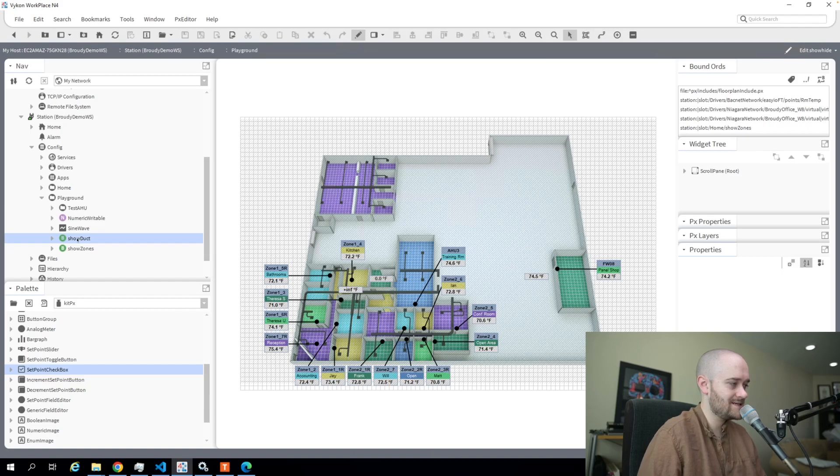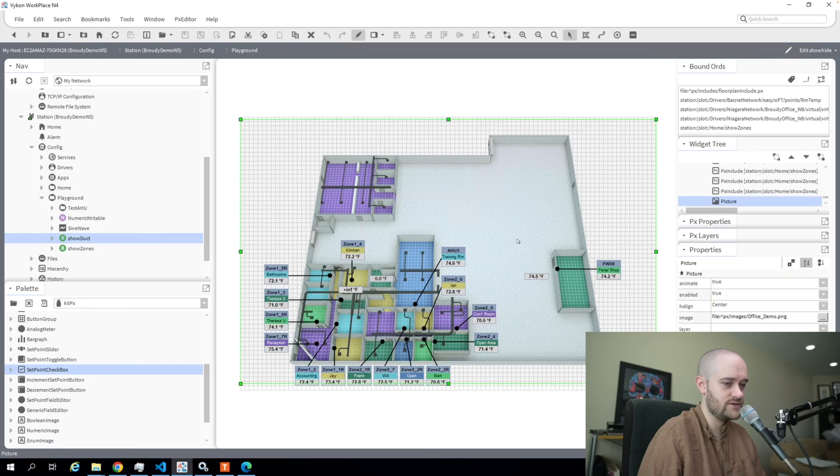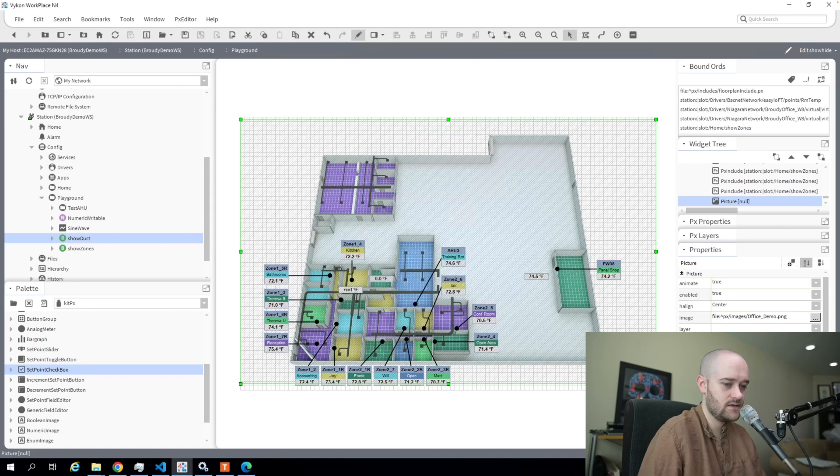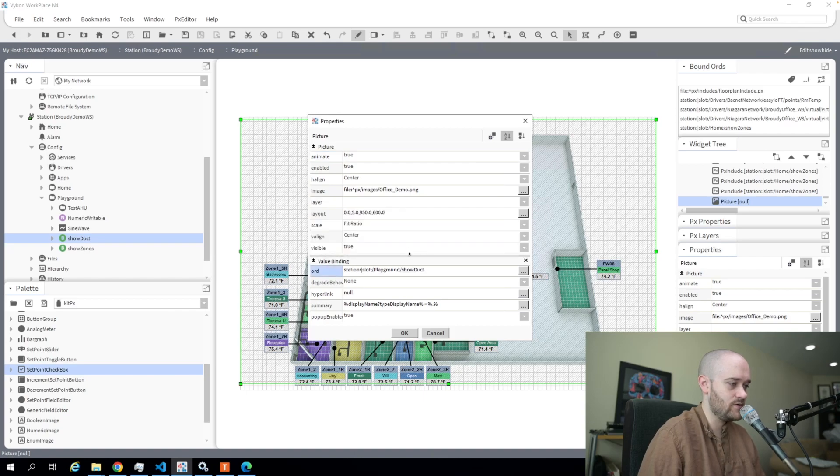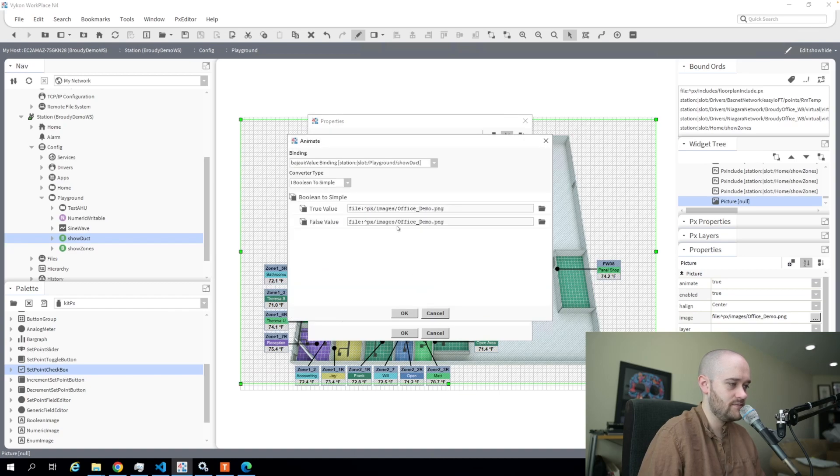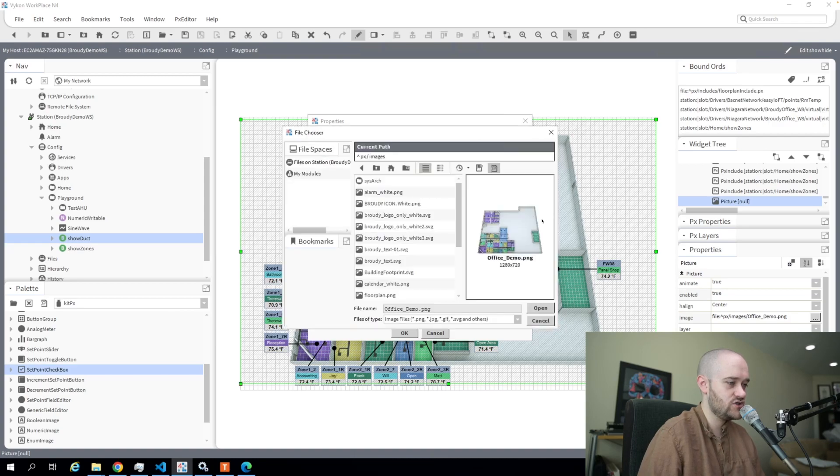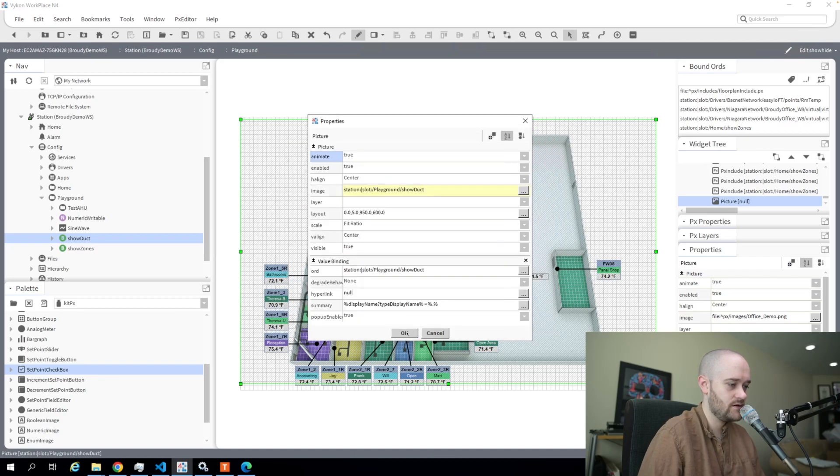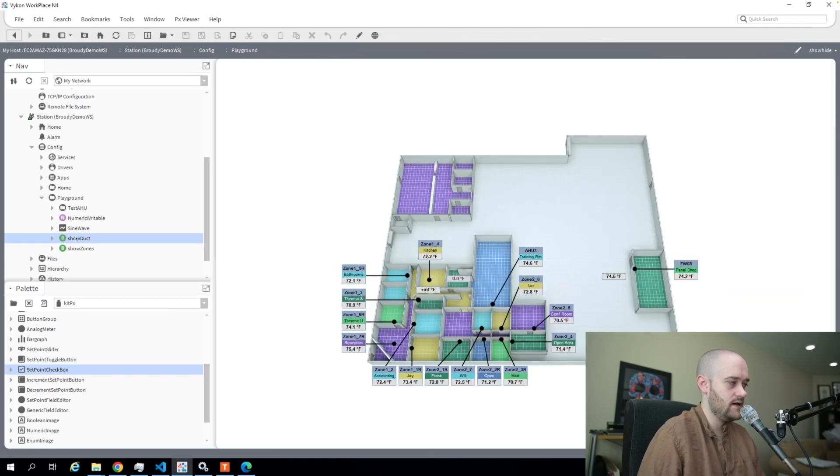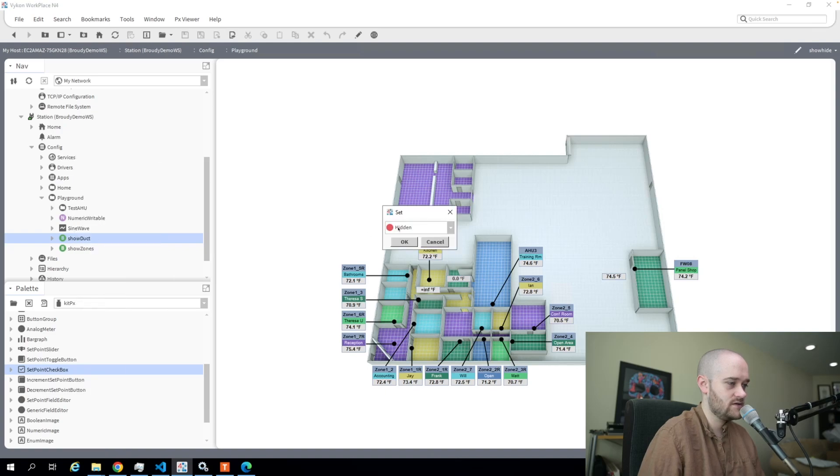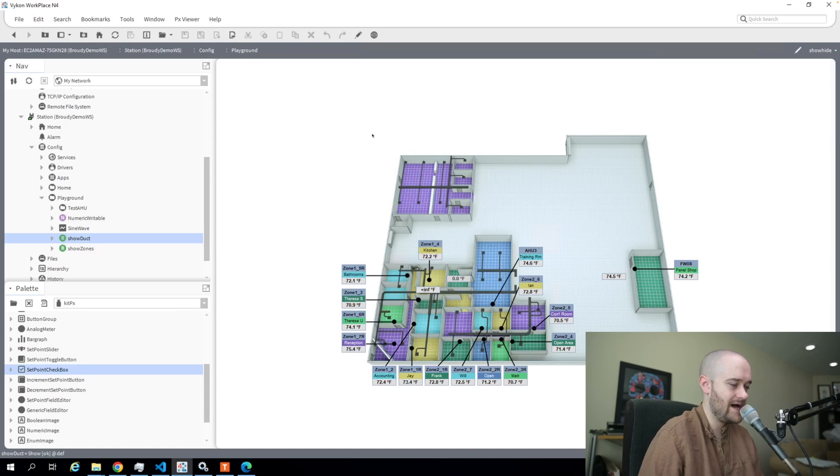As an example for the show duct, I'm going to come in here to my floor plan image, add in a new value binding, and paste in that point as my ord. I'm going to animate my image on it because I have this image which is my show when I'm showing my ductwork. For the false image, I also have a version of the image without the ductwork. If I get out of here, you can see it went back because this is already set at false, so it's hidden. Now if I make it show, there you go, we're showing it. So a little bit of interactivity that we'll be able to do, and we'll add some controls on the screen so that we can make that happen easily.